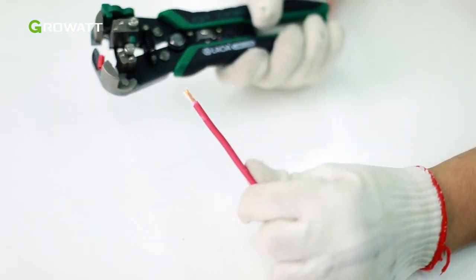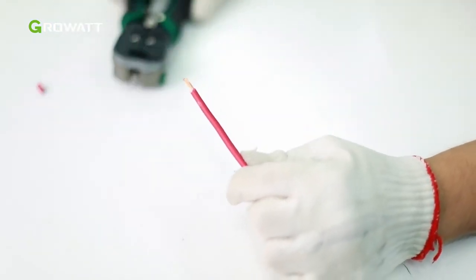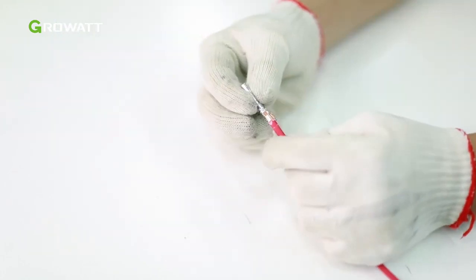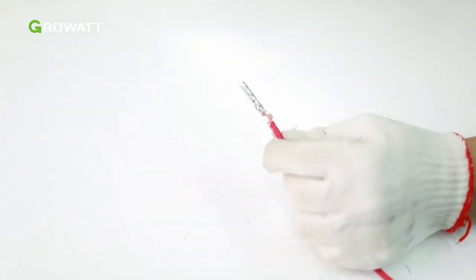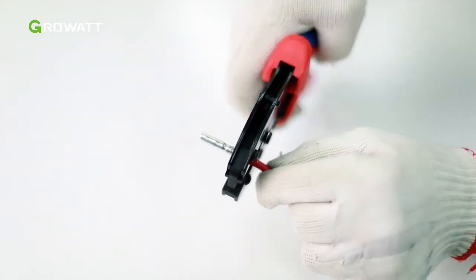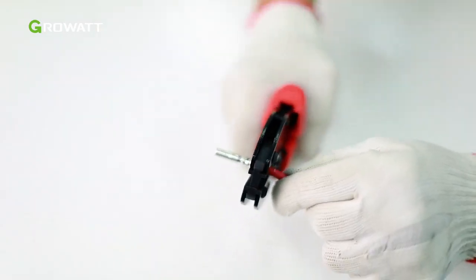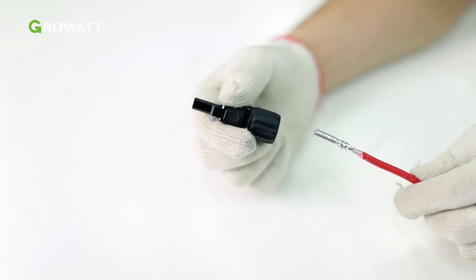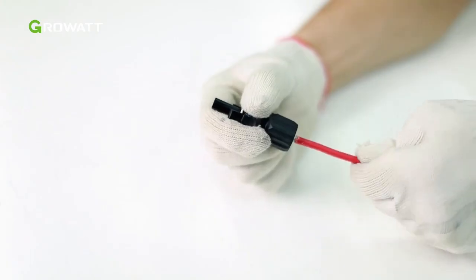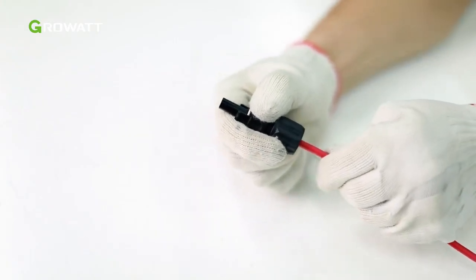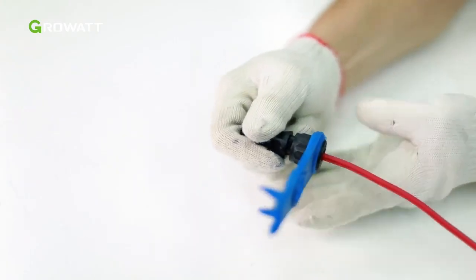Strip 6 to 8 mm of the insulation layer of the DC cables. Insert the exposed core wires into the crimping area of the wiring terminal and crimp them using a crimping plier. Route the cable through the cable sealing sleeve and insert the insulation sleeve until it snaps. Then tighten the locking nut.